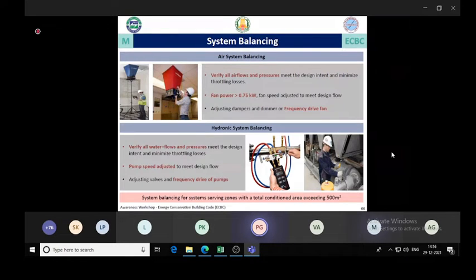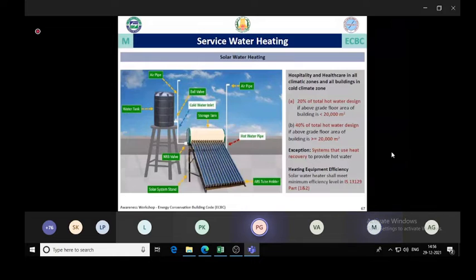Okay. And it is also mandatory to do a proper commissioning, which will include an air balancing and hydronic system balancing. These reports should be submitted for compliance. And in hot water system, especially for hotels and hospitals, out of the total hot water requirement, it is mandatory to have 20% from solar water heating system. So this again could be a little bit of a challenge when we have a huge hospital and if the roof area is not sufficient, then meeting this compliance could be a little bit of an issue.